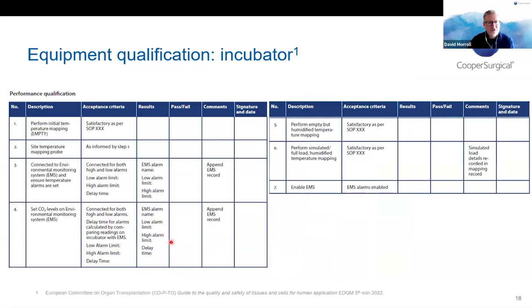And then the performance qualification, which, as I've said, is the one that we are interested in terms of reflecting real world performance. So this is around temperature mapping empty. You might repeat it during use.